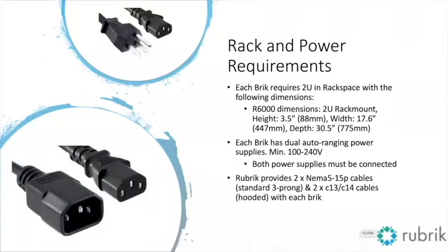Now we'll talk about the rack and power requirements for the Rubrik installation. Each brick requires 2U of rack space with the dimensions listed on this slide. Each brick has dual power supplies that auto-range from 100 to 240 volts.